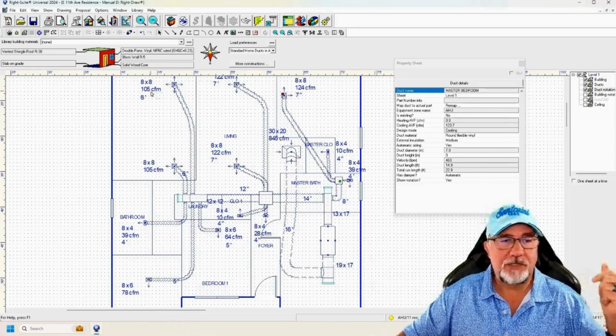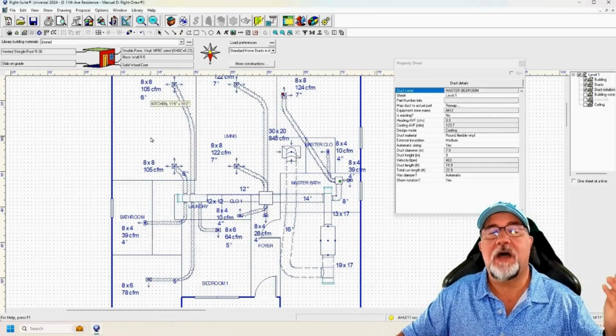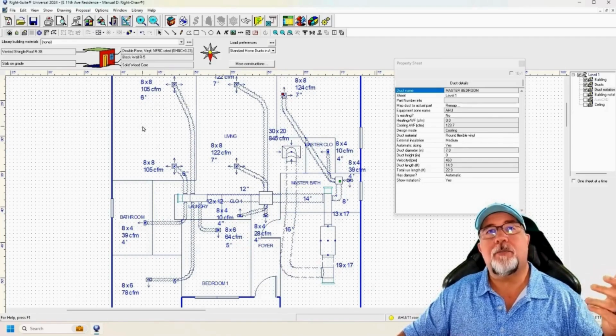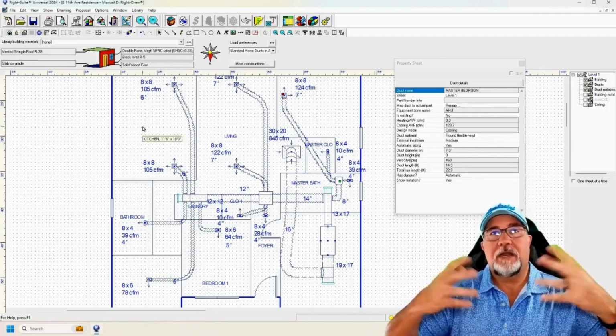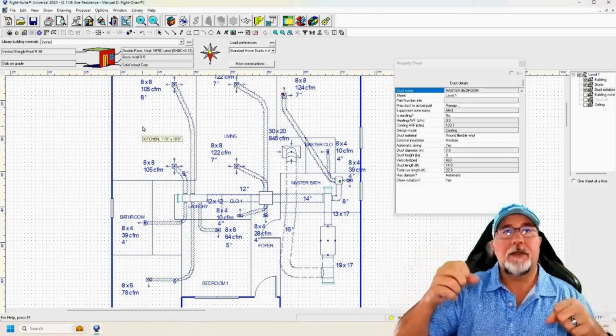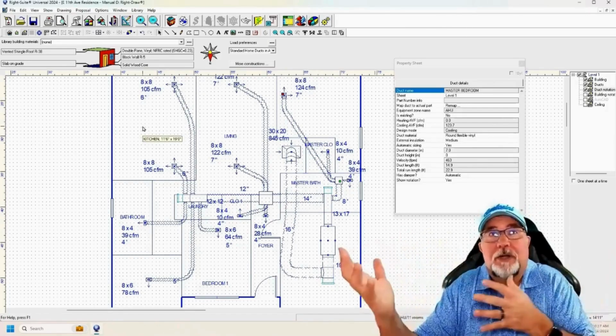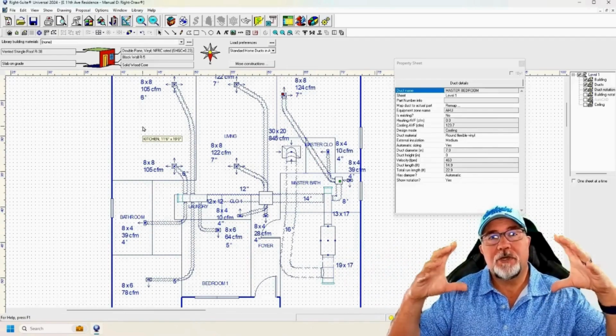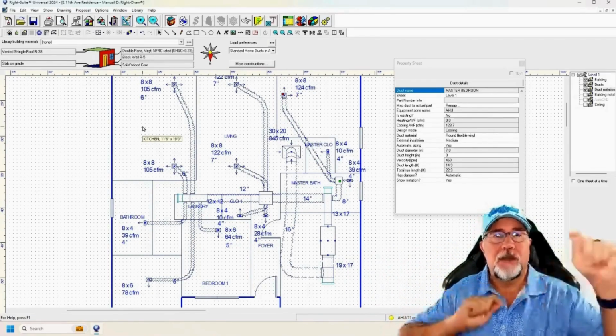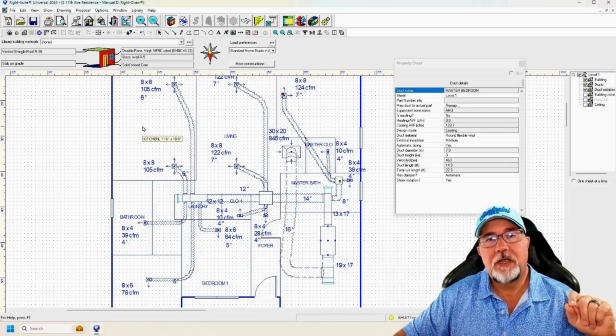So your kitchen is supposed to have 2 grills at about 105, but if they don't install these properly, then they could get a lot less than that. And if they're not dampering, it could be even worse, or it could be too much air. So that's where the importance of proper duct design and proper air distribution is extremely important.